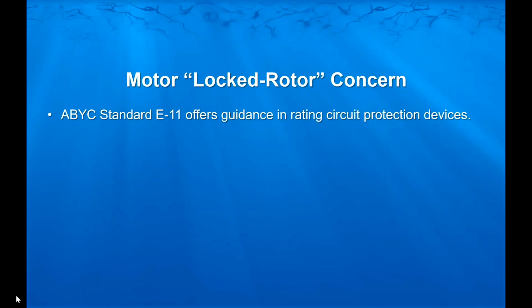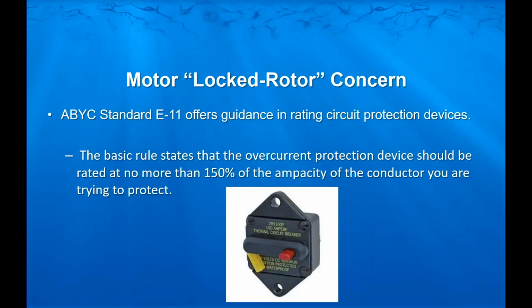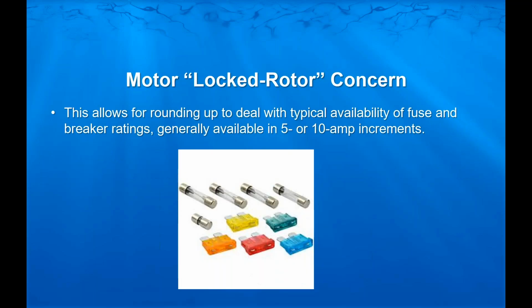One very specific subject related to overcurrent protection is what's called a locked rotor concern. The basic rule of our overcurrent protection is that it be rated at no more than 150% of the ampacity of the wire that you're trying to protect. Again, we are trying to protect the wire with our overcurrent protection. Just like your house, you have wiring that goes to a plug. It's got a 15 amp breaker in the panel. They don't really care what you plug into that plug. If it's too much, it's going to trip the breaker. Essentially, the same thought in both. So we're trying to keep that length of wire from burning up. That's our main concern, is to eliminate how much wire can burn up in that boat if something goes wrong.